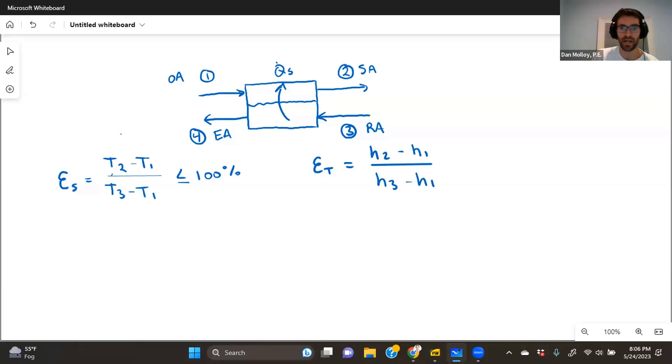And by the way, it's also possible for an energy recovery device, not as common that they'll ask this, but they could certainly ask it, that they may want to know the latent effectiveness. And that would be the same thing with humidity ratios. And the same reasoning applies. So the humidity ratio at 2 minus the humidity ratio at 1 divided by the humidity ratio at 3 minus the humidity ratio at 1.